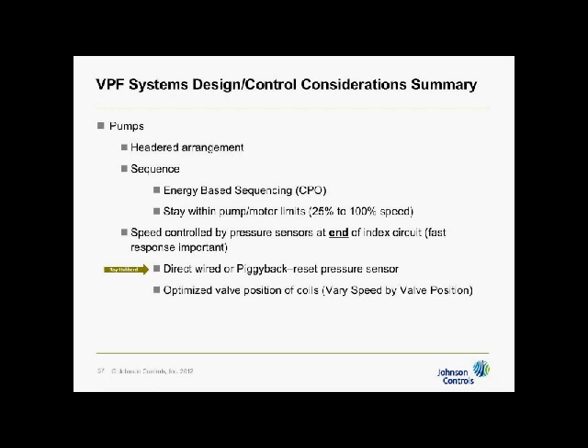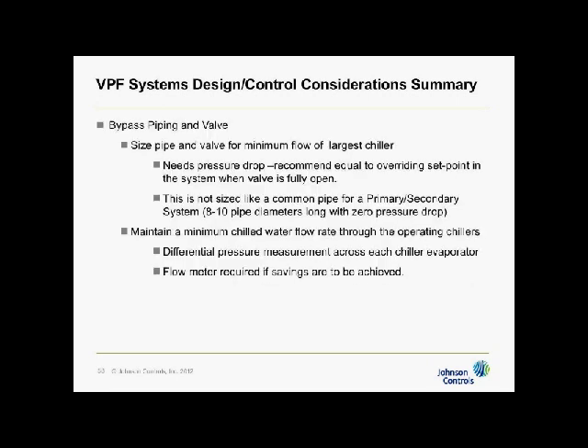The more optimal way to do it is to vary speed by valve position. You find the worst valve in the system because if you're monitoring all of them, you can find the worst one. And you want only one valve to be near 100% open, and so you control the speed that way. That way you can slow down even farther at every load, just about every point, just a little bit, but it squeezes some more energy. Okay? The bypass piping that we're looking at that maintains minimum flow through the chillers. You size that pipe and valve for the minimum flow of the largest chiller, or of the operating chillers if you happen to have more than one that are operating at a condition where you're actually at minimum flow. It can happen, but usually it's just one chiller.